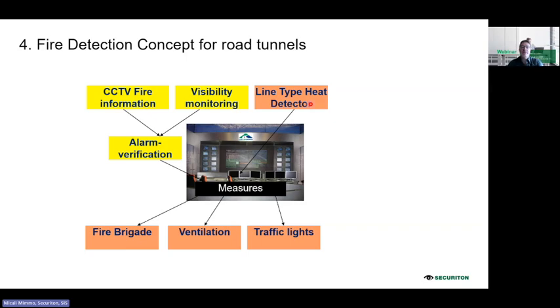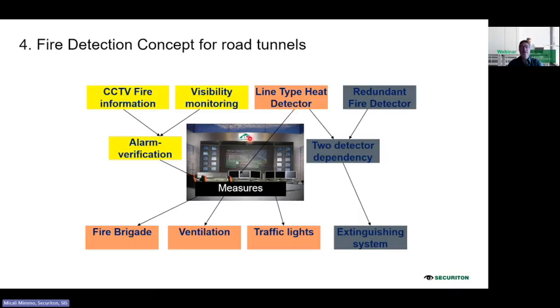This is probably the most important system, because only when we receive the alarm can the system trigger the ventilation and trigger the traffic lights. That means putting the light on red to prevent other cars from entering the tunnel, and at the same time alerting the fire brigade. And if the tunnel is equipped with an extinguishing system, then if you have a second alarm, this extinguishing system will automatically be triggered.